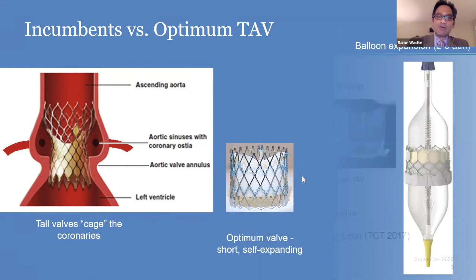We've already demonstrated preclinical superiority in the 2 standard tests. One is the accelerated wear test, also known as the durability test, which is run at about 1 million cycles a day, or 10 times our natural heart rate. The FDA requires 200 million cycles, which is run over 6 months and simulates about 5 1/3 years of life. Our valve has surpassed 24 years with no signs of degeneration. And in the same test, we had a control surgical valve, which started showing wear or degeneration at about 15 years, which is pretty similar to its clinical use. So we think it's pretty accurate.